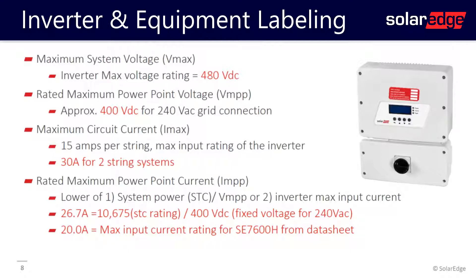The last and most tricky calculation is the IMP. You're required to do a calculation and a lookup and choose the lower of the two values. For the calculation, we take our system power at STC and divide it by our voltage at maximum power. In this example, we took our system power of 10,675 watts divided by 400 volts DC and we find 26.7 amps. Then we do our lookup, which says for the 7.6 HD Wave inverter, we have a maximum input current rating of 20 amps. We choose the lower of the two values and put 20 amps on our label.